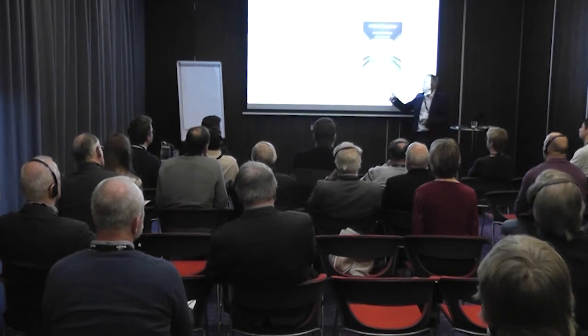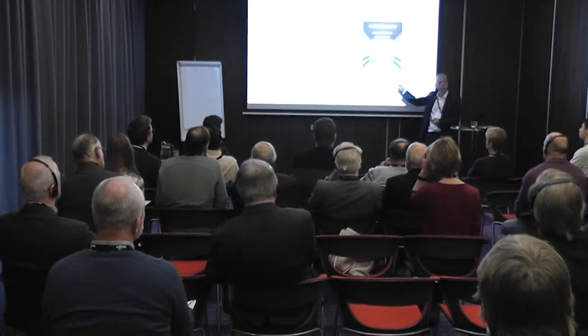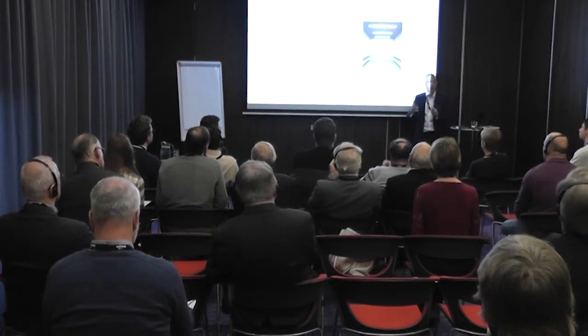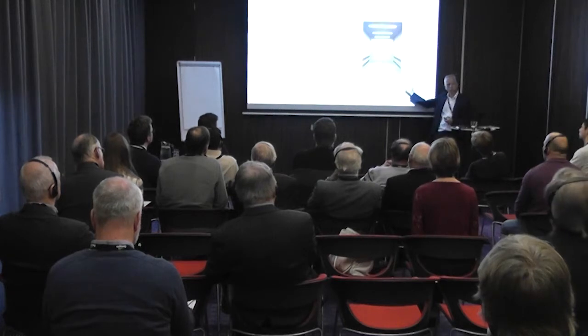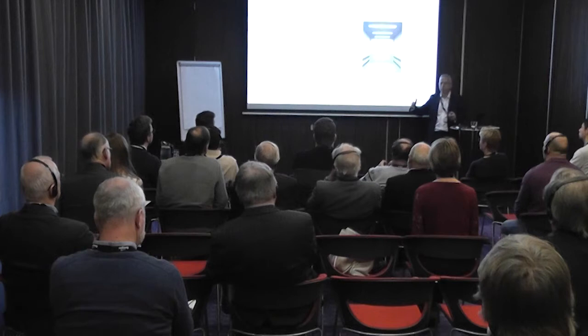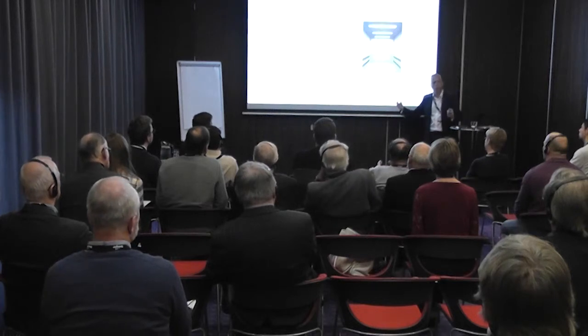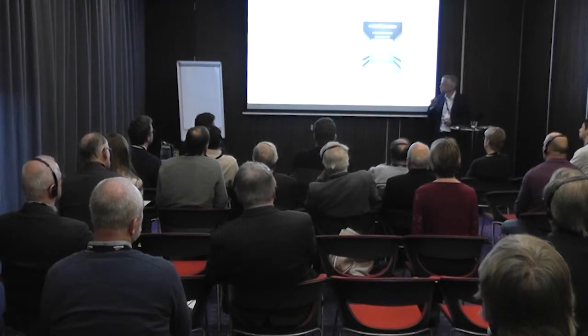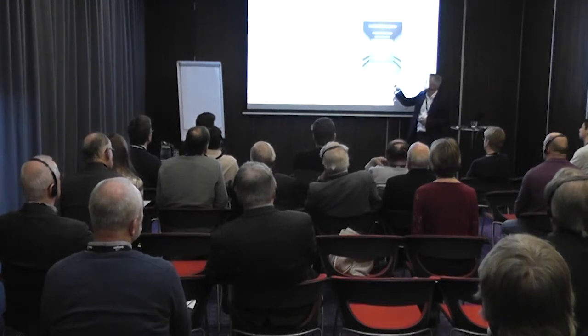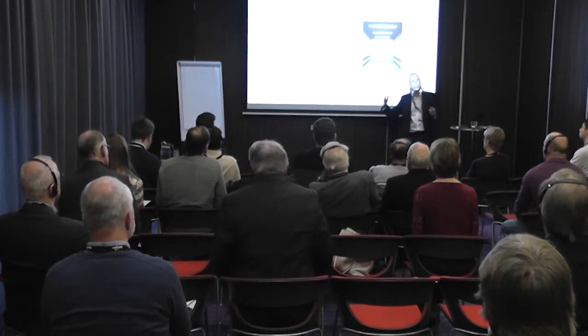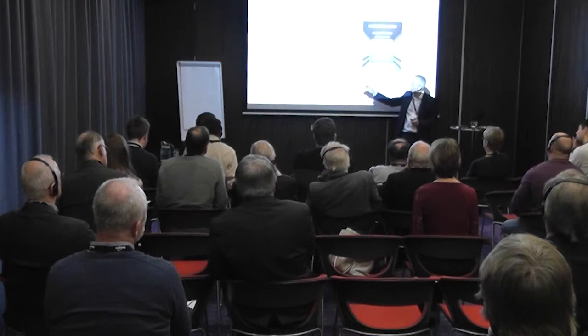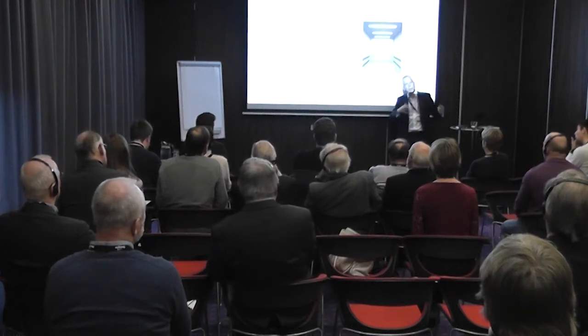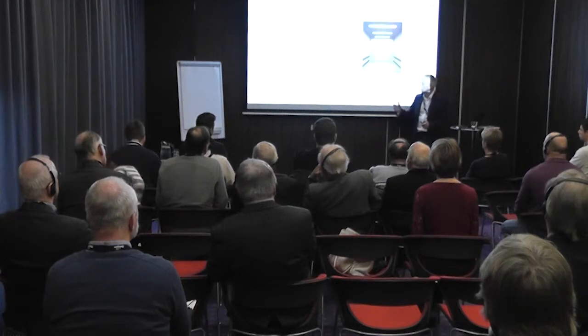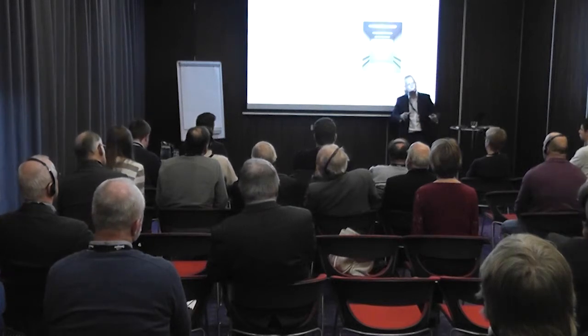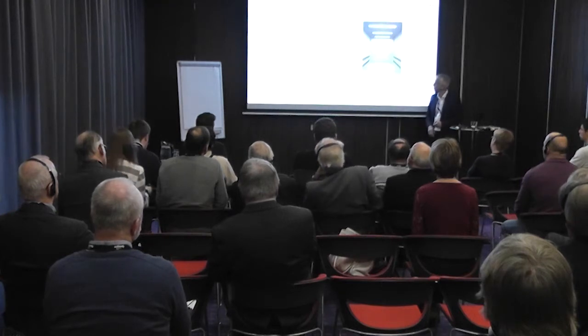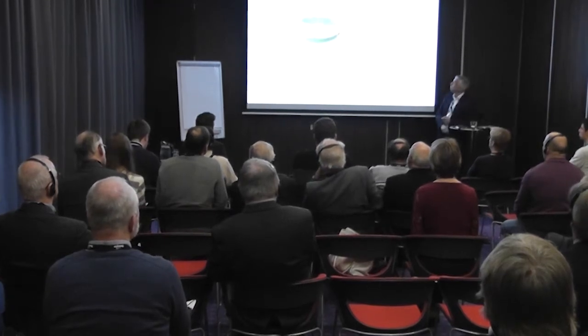Our view is, look at the goods lifts - lifts installed in buildings to bring up equipment or goods needed by tenants on their floors, like furniture or photocopiers. They tend to use the goods lifts for those. What we found is, if you have a 3,000 kilogram rated lift, you can actually use that for removing and replacing most of the equipment, including air handling units, which you then break down into smaller sizes.